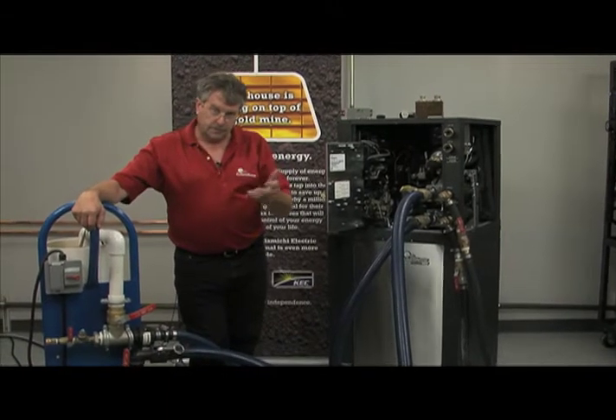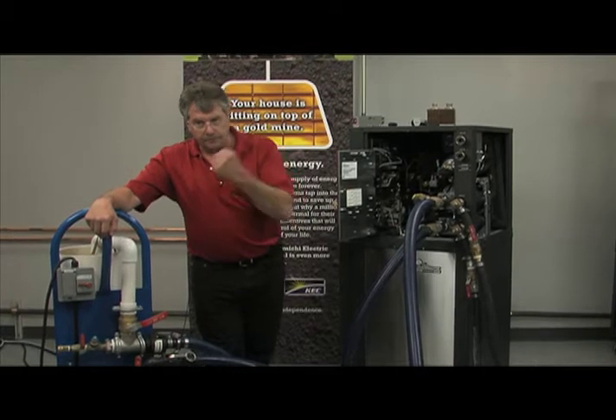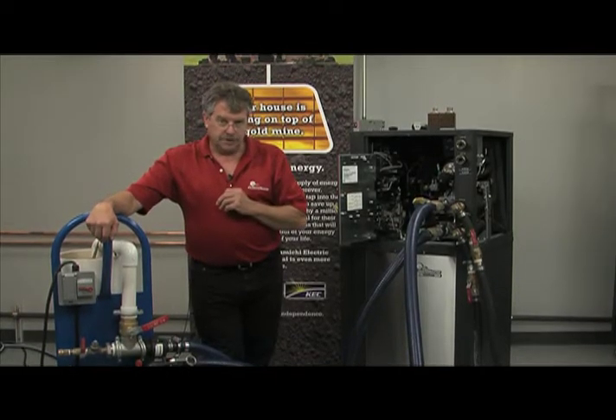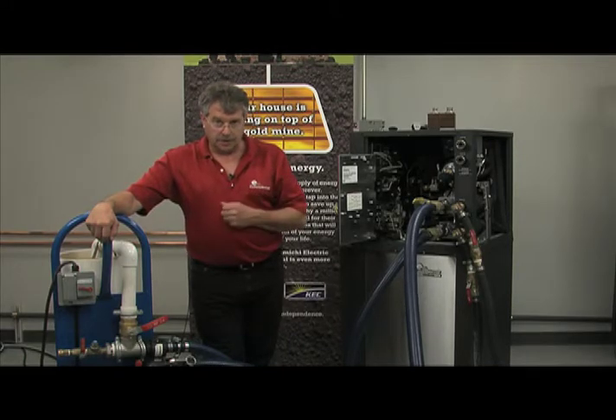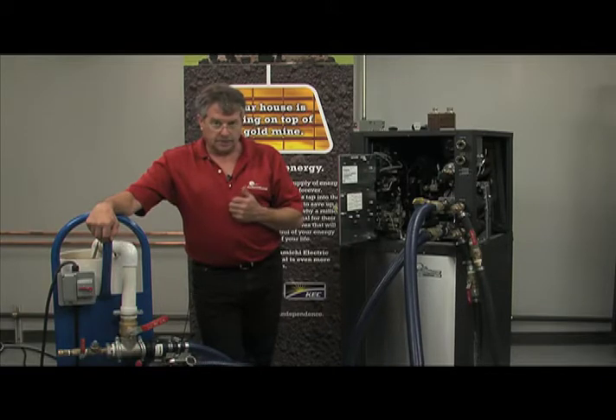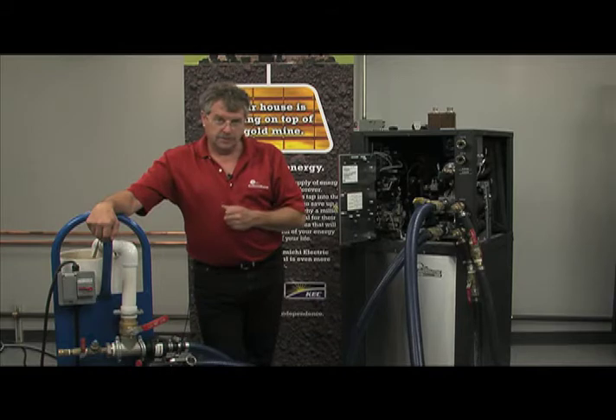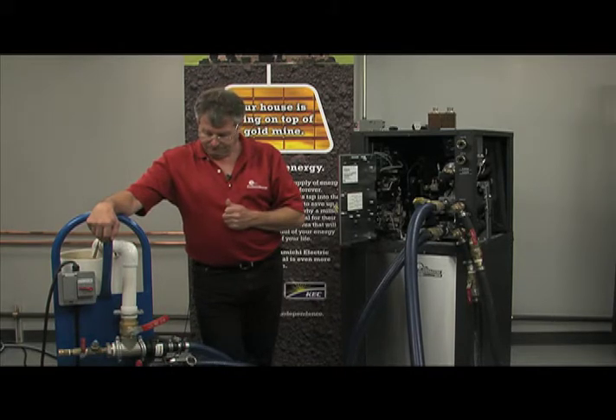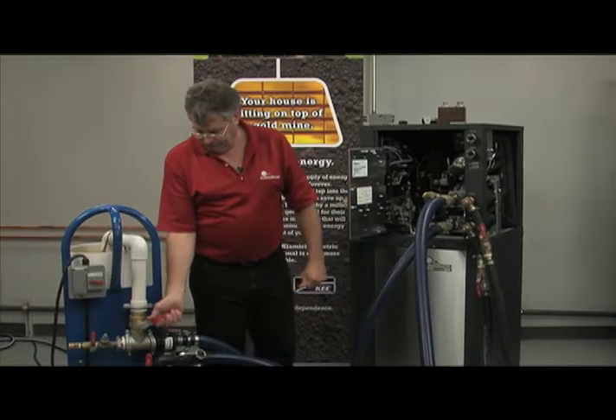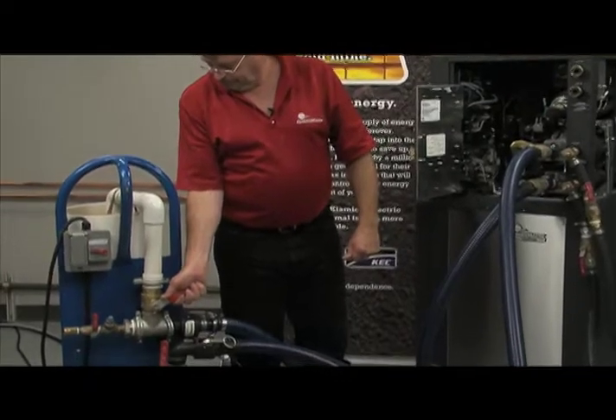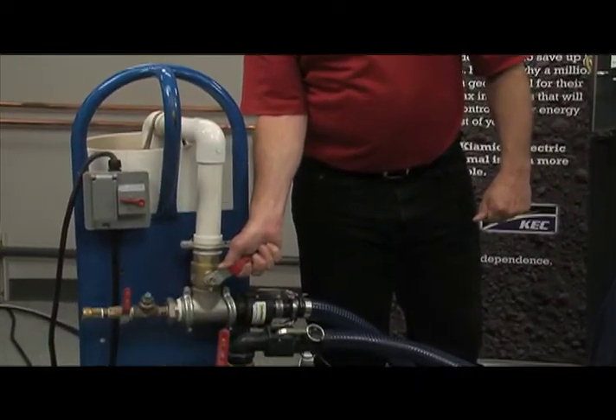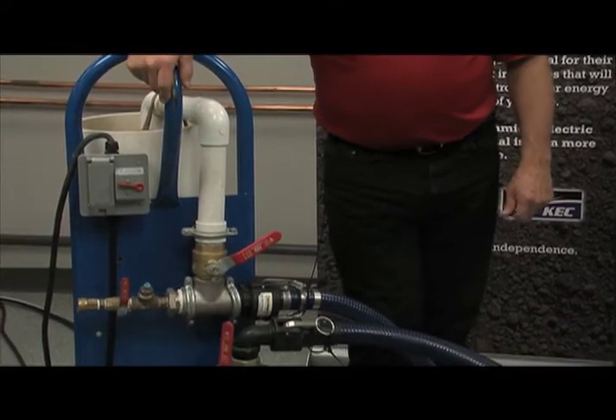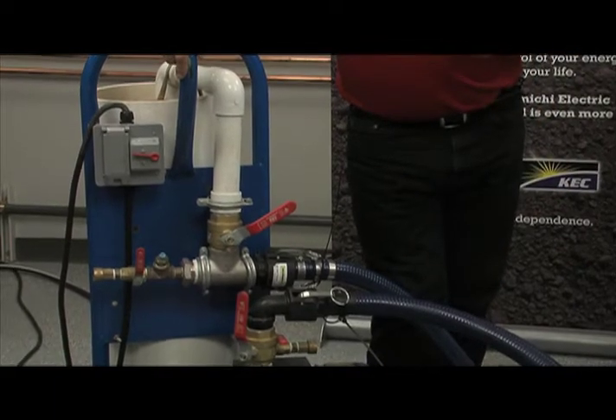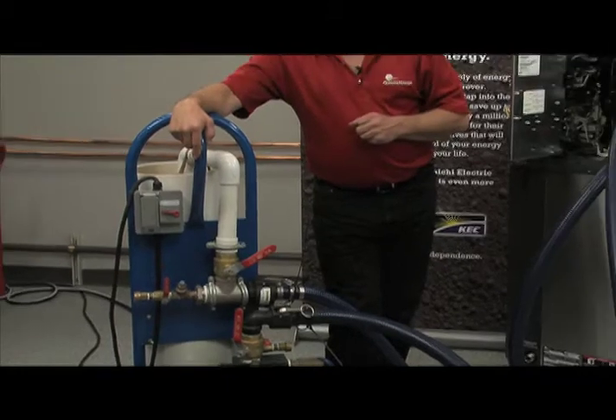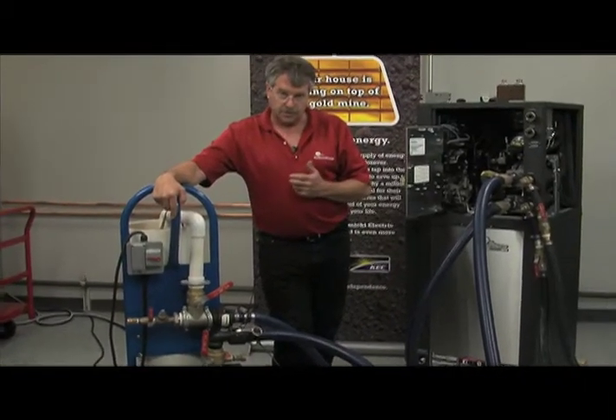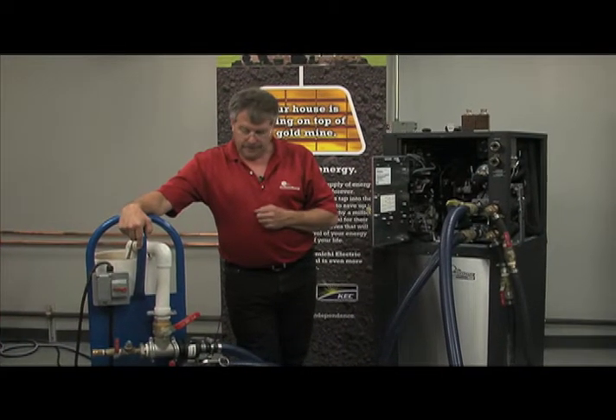So it's important not to rush this, because quite honestly, getting in a hurry, doing what you're probably used to do, full throttle going through your typical heat pump, well, you're just going to have to go back and make some corrections on that flow sensor, replace the part, and go through this process again. So again, take your time, do it right, save yourself some labor down the road. So I probably have this valve in, I don't know, 40–50% position. We'll go through a couple of deadheading procedures as we normally do to validate whether we have the air removed from the inside of this unit.